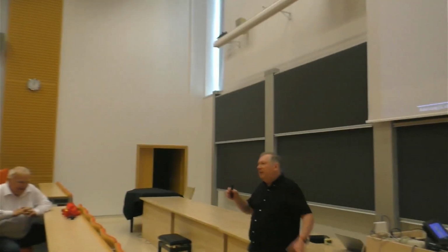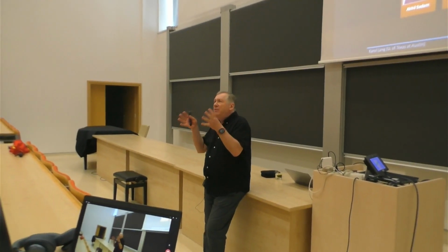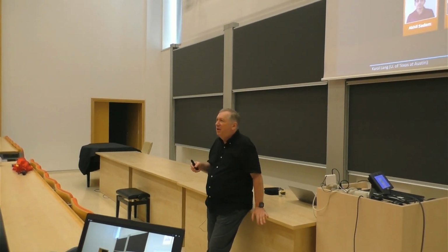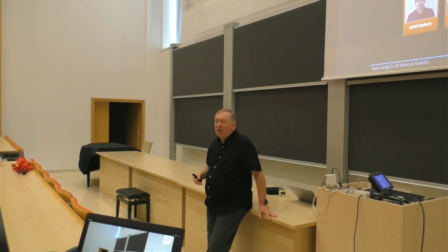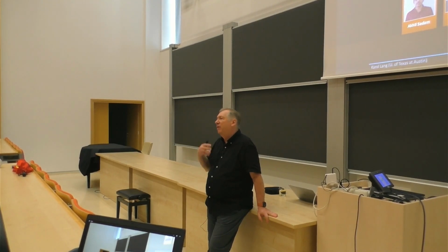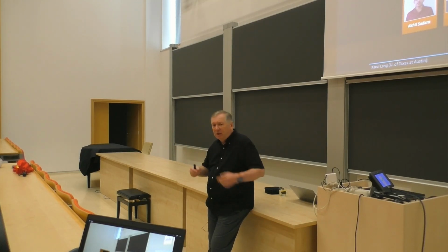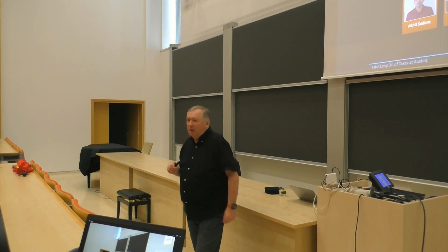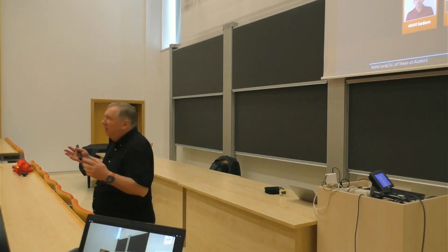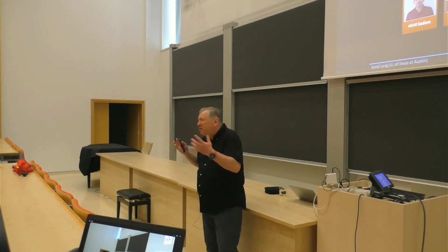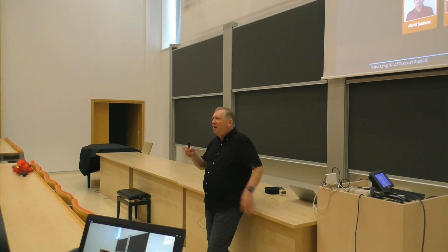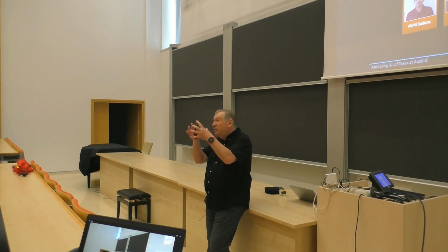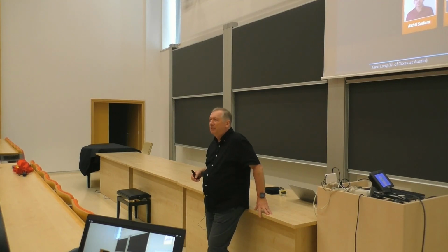So if you look at it, I have not shown the parameters of our PET scanner because it is being evaluated, and I don't want to quote numbers that we cannot have a clear demonstration of. But roughly speaking, our resolution, and I'm going to cut off my microphone and state it, is about 2 millimeters, okay? So it's pretty good, and I think we can do much better, in fact. Much meaning maybe 1.6. There are indications that in some central portion of the so-called field of view, it can be as good as 1.6.